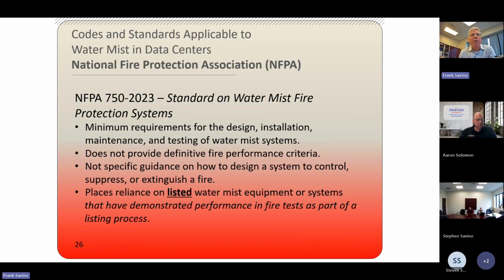So what are some of the codes and standards that are applicable to water mist systems in data centers? NFPA 750 is a standard for water mist systems. It gets into the minimum design requirements for design, installation, maintenance, and testing. NFPA 750 doesn't really provide definitive performance criteria. It is very general, and it relies on systems that are part of a listed product with full-scale fire testing. It's very general and generic.